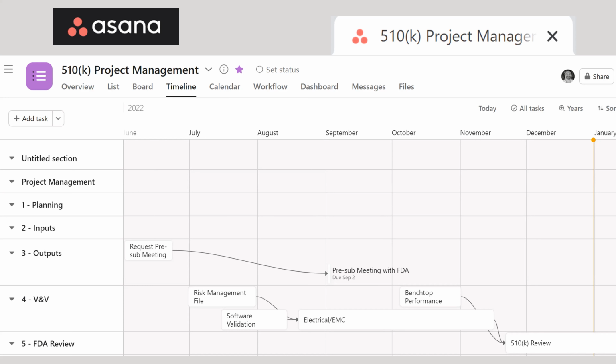Well, what is the last test report that I'm always waiting for? It's either sterilization validation, biocompatibility testing or electrical safety. Well, this particular example I'm using here is a non-sterile product, so we don't have any sterilization validation. And we're going to go one step further. We're going to also say this device doesn't have any biocompatibility requirements either, because it's non-patient contact.